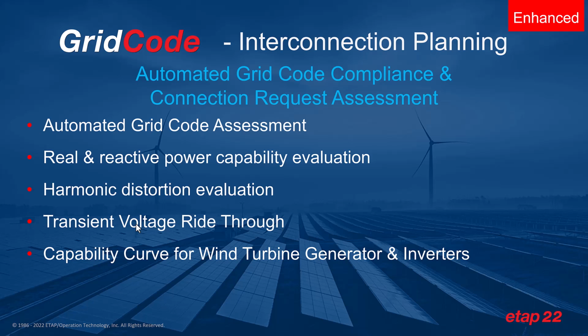renewable energy systems. The ETAP grid code in ETAP 22 utilizes a model-driven electrical digital twin with automated analysis, predictive calculations, network optimization, validation processes, and intelligent, secure hybrid power plant control to ensure local grid code or standard compliances are maintained throughout the power system design as well as operations lifecycle. In ETAP 22, you can automate the grid code assessment, including the real and reactive power capability evaluation. You can also perform harmonic distortion evaluation, transient voltage ride-through, and consider capability curves for wind turbine generators and inverters.